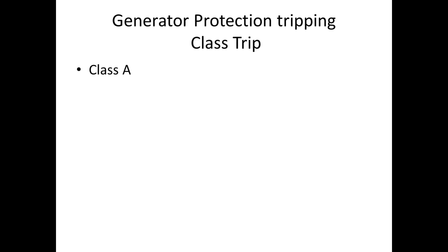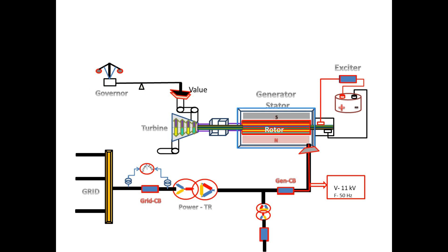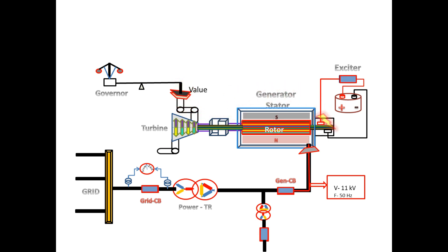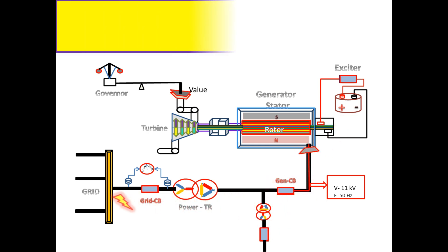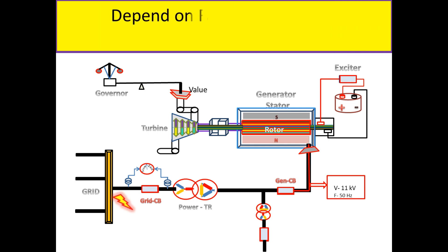First, we are going to see why we use different tripping classes. In this generator layout, there are many circuit breakers associated with generator protection, and there is a possibility of getting faults at various places. It is not necessary to trip all circuit breakers for all types of faults, so depending on the fault, it should trip the corresponding circuit breaker only.